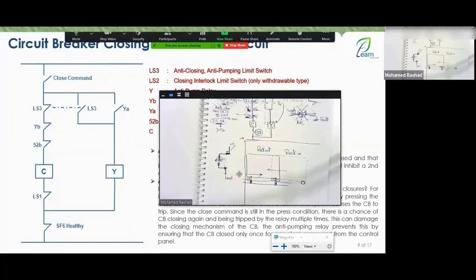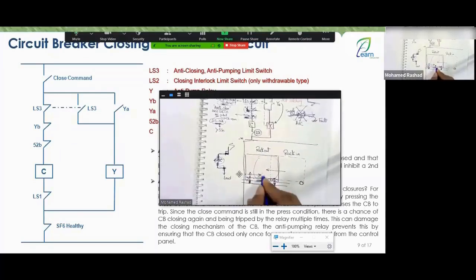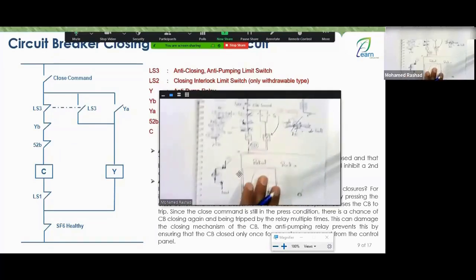Very good. So now, if the breaker is in between, this lever, engineer, you open the breaker, so this lever is pulled up now, right? The breaker is in between here. So when you want to do what? You want to close the breaker while it's in between. When you try to close it, you'll find this lever hits where? In the groove, so you won't be able to close the breaker. So mechanically, you won't be able to close what?